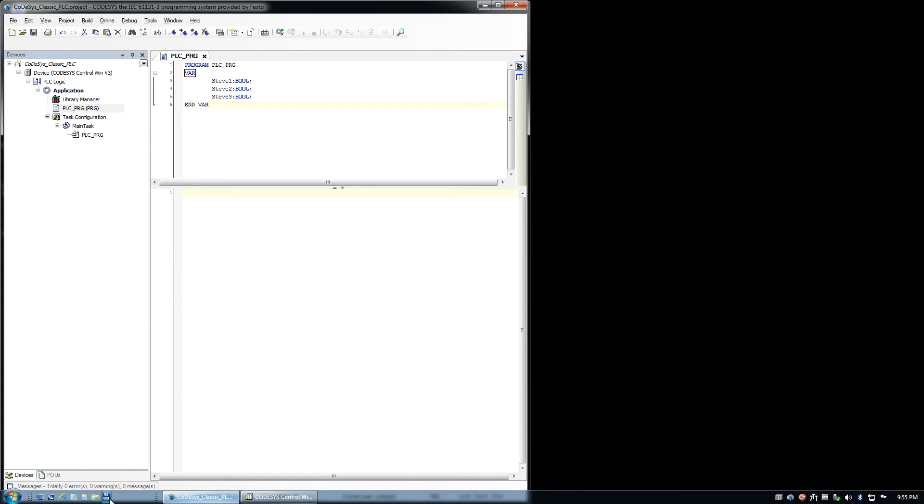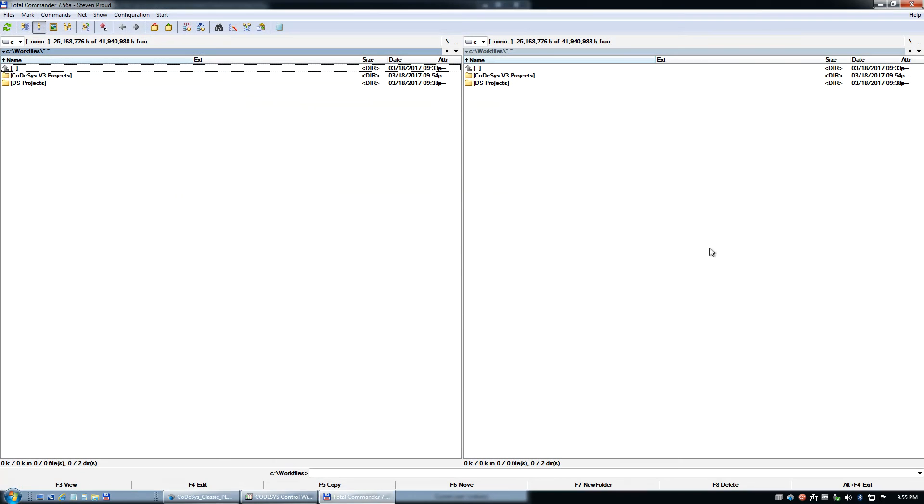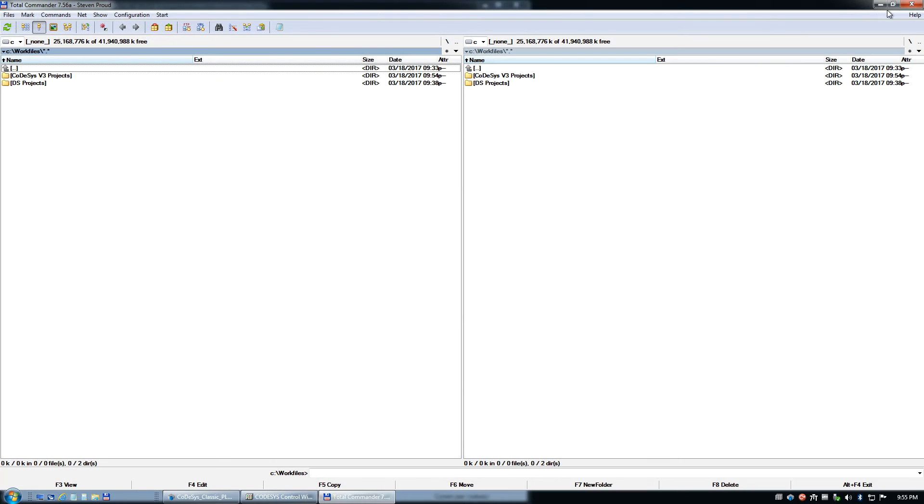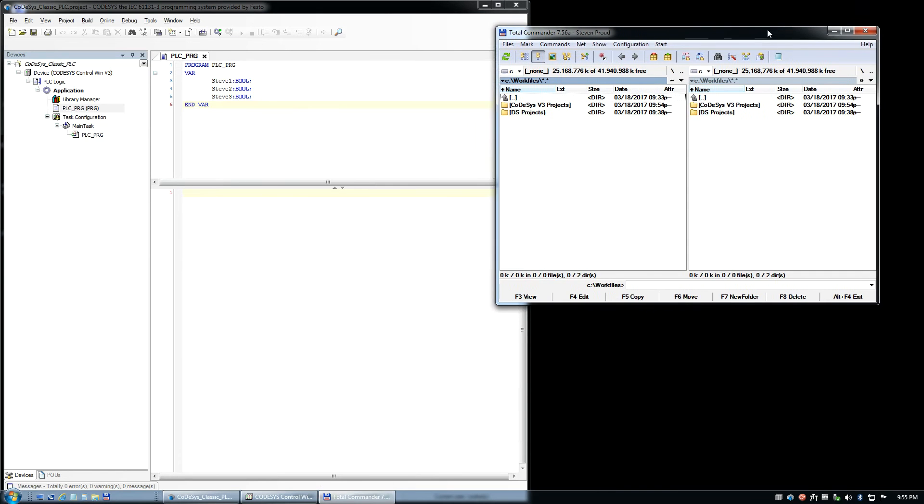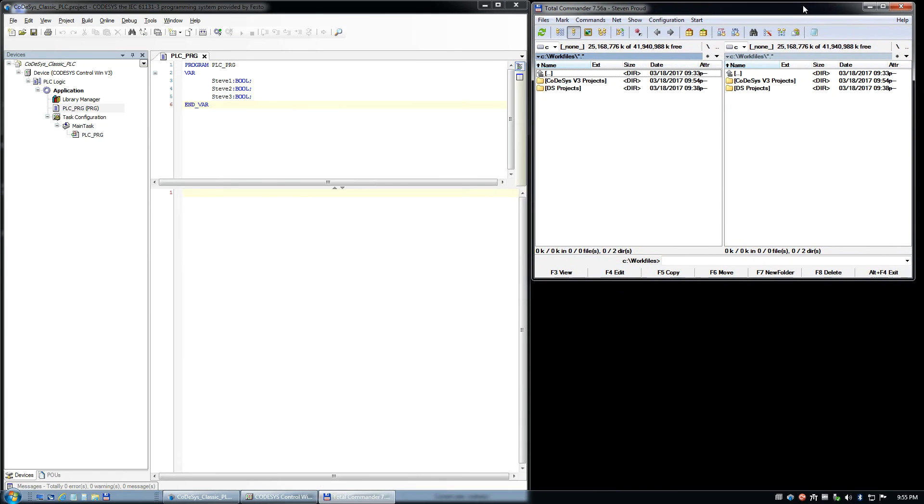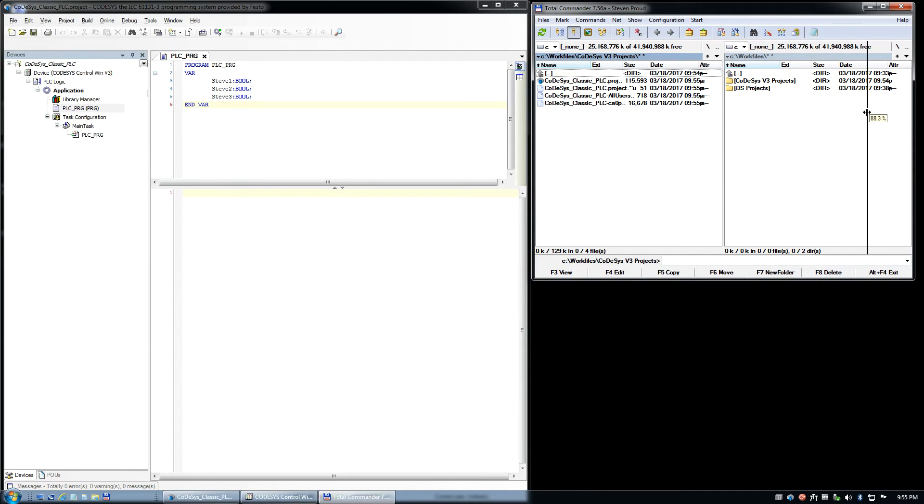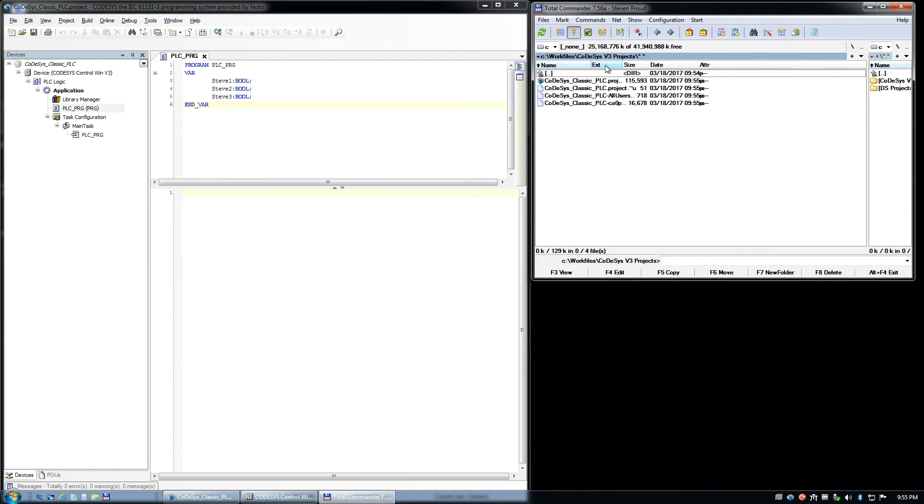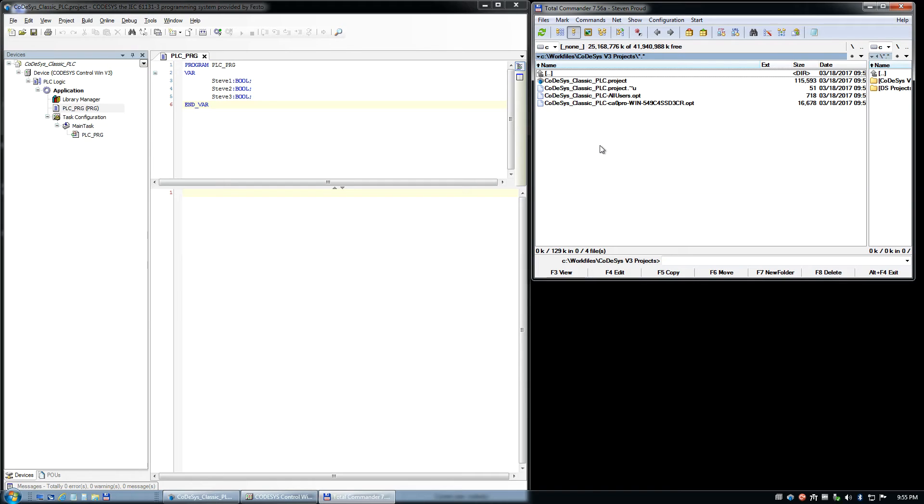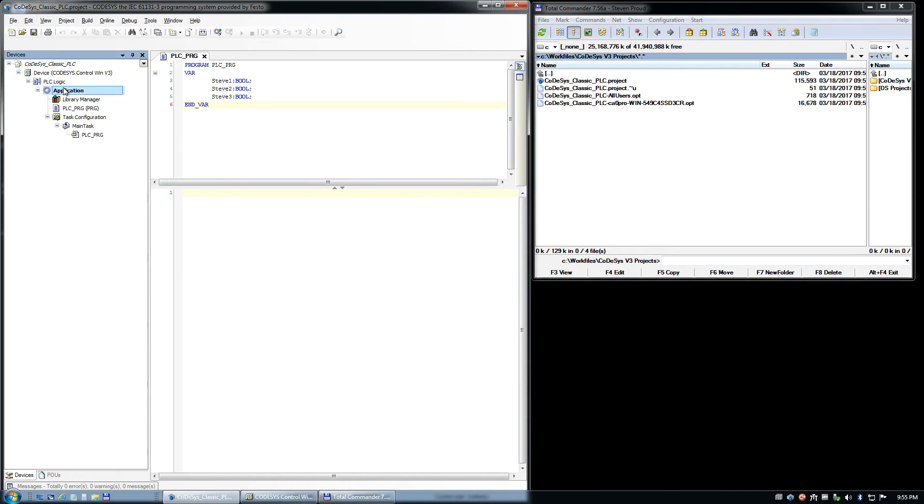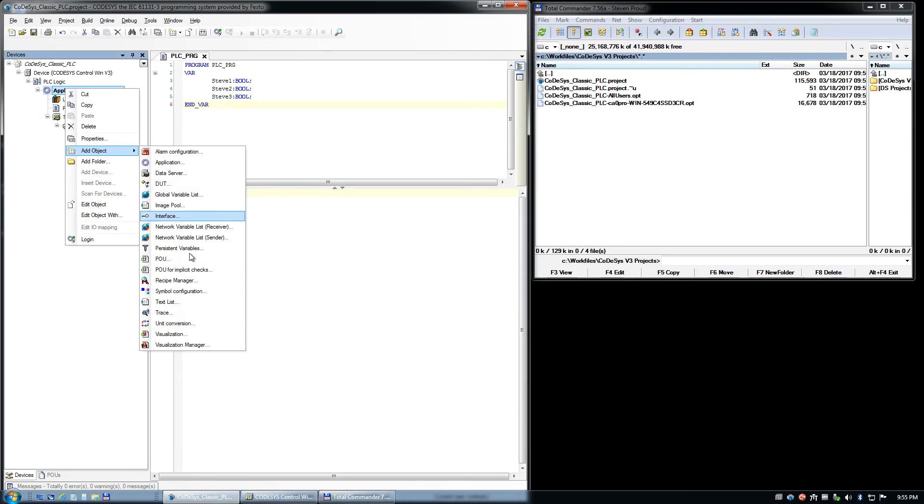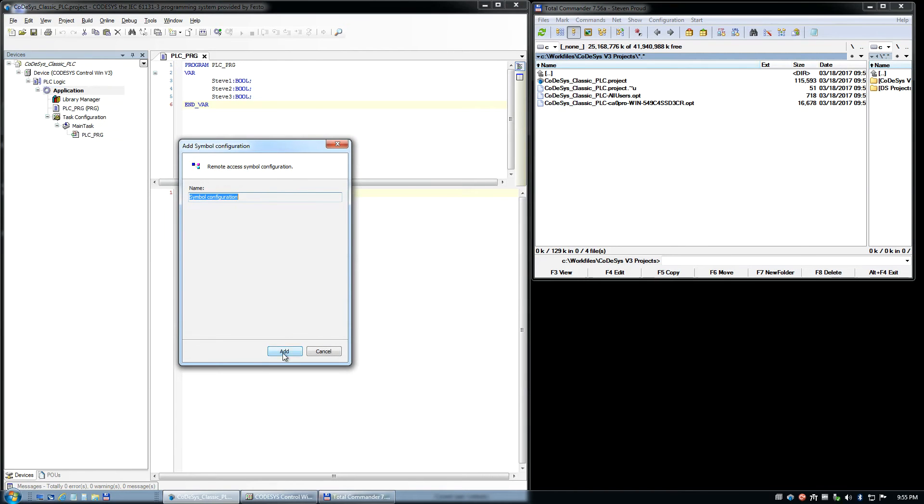So now show you the directory here. So this is the directory we're storing our PLC program in. Move this over here so we can see what we have in each. In order to get tags from the PLC to or in order to get the variables from the PLC to the tags in the HMI, we need a symbol configuration, so we need to add a configuration.